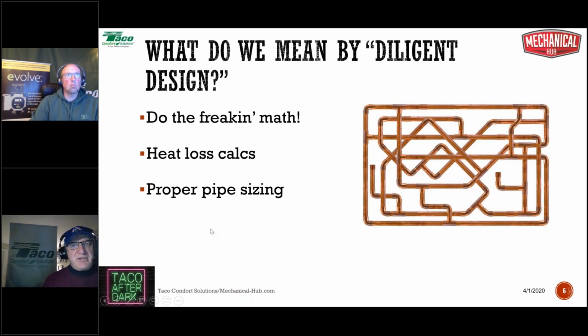1-inch pipe and 1-inch fittings are less expensive than 1.5-inch and 1.25-inch fittings. 1-inch air separators are also less expensive than 1.25-inch and 1.5-inch. By doing the math, you'll know whether you need 1-inch or whether you should go up to 1.25-inch.